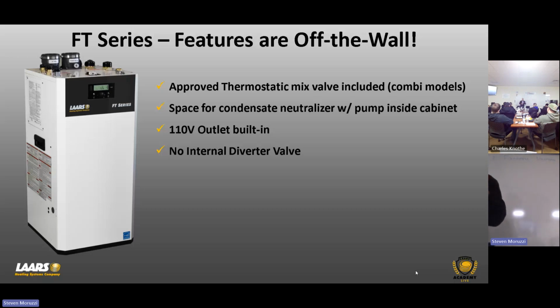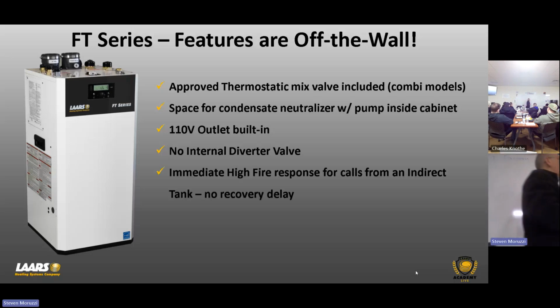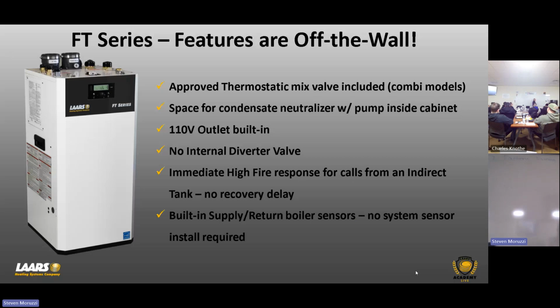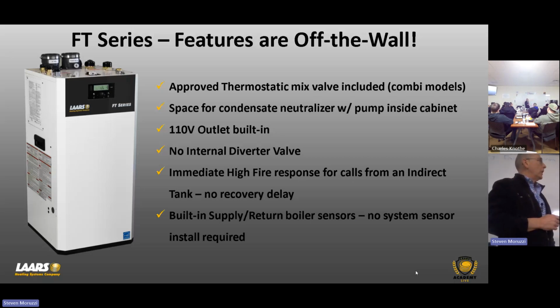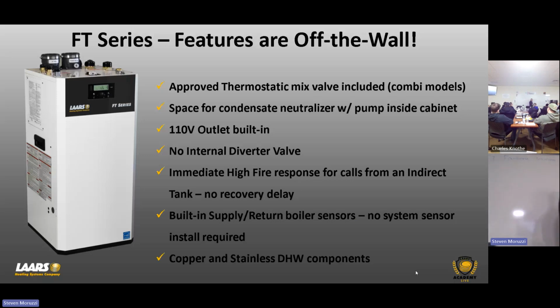All right. So with this, there's no diverter valve. What that's doing is allowing us to provide heat and hot water simultaneously. Okay. So no diverter valve. And we have built-in supply and return sensors. No system sensors required.